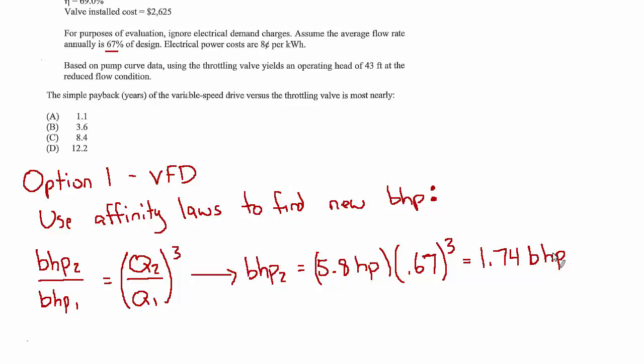We can probably neglect that for this problem and just take the BHP as the electrical power. We do need to account for the efficiency of the pump, where that turning of a shaft, that brake horsepower, then becomes water horsepower or hydraulic horsepower. So we will include that efficiency between the shaft and the water, but we'll neglect the efficiency between the windings of the motor and the shaft.